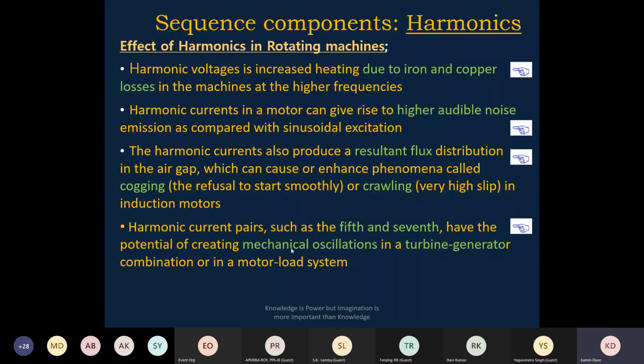The harmonic current pairs such as the 5th and 7th have the potential of creating mechanical oscillation in a turbine generator combination or in a motor load system. 5th and 7th harmonic अगर जनरेट कर रहा है तो that will be a severe mechanical oscillation in turbine generator. It is a torsional torque जो हम बोलते हैं, that is how the torsion is there.